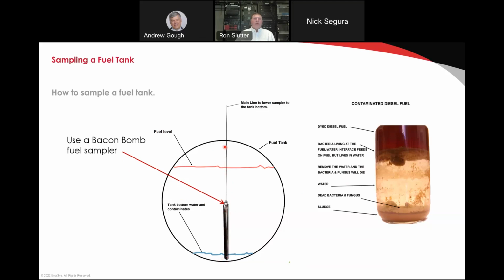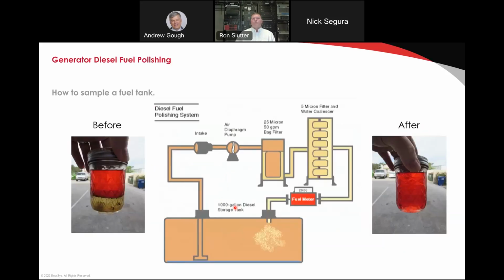Most of the time, generator guys are going to push a little white tube in here and pull fuel out with a little plunger, and that tends to just take fuel that's at the top of the tank, which is almost always going to be good. If the fuel up here is bad, you've got a real problem. You need to make sure that you're asking for the use of this fuel sampler from the bottom of the tank. Very important.